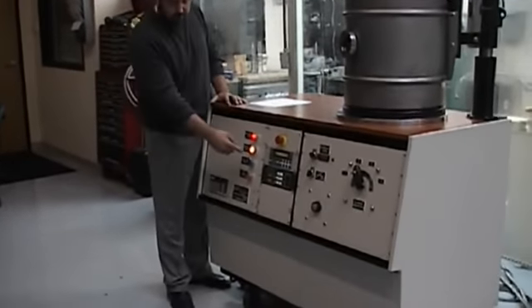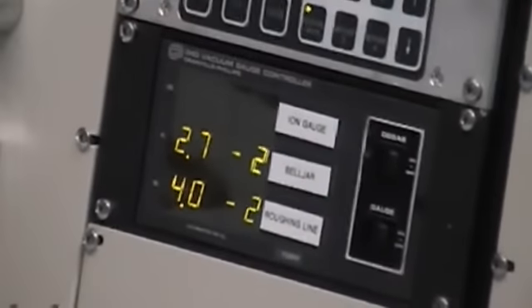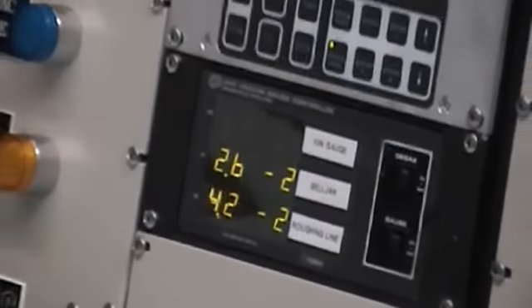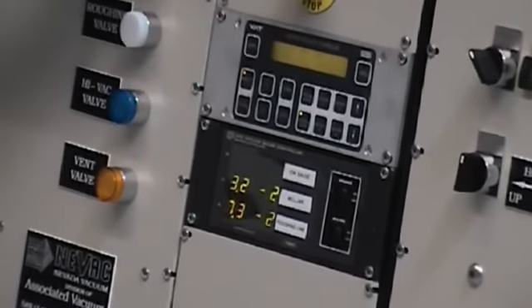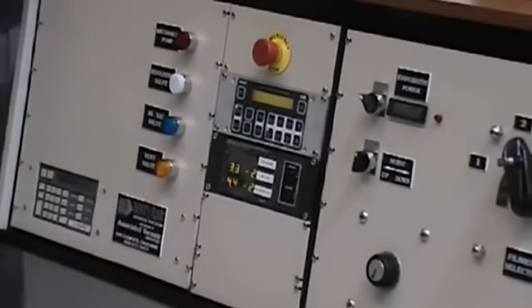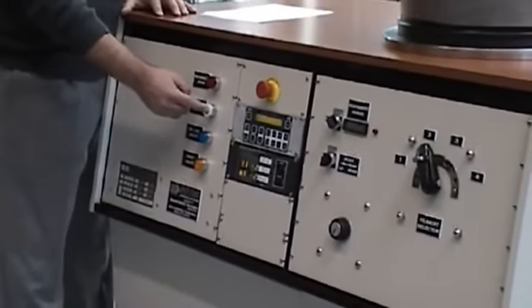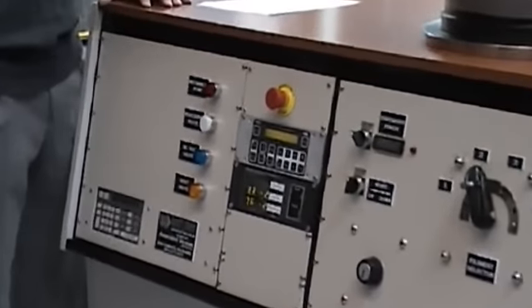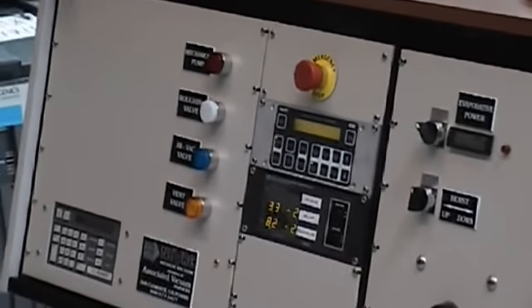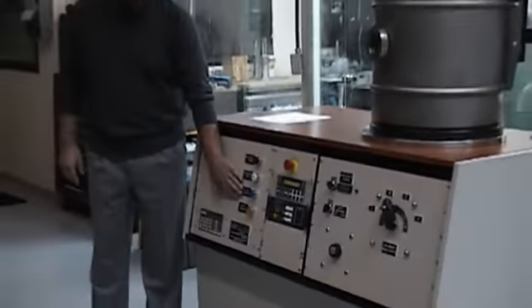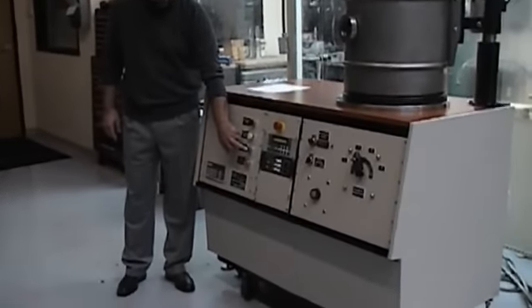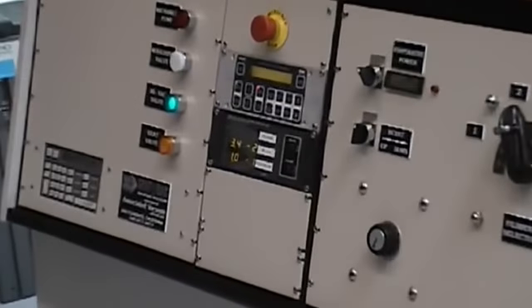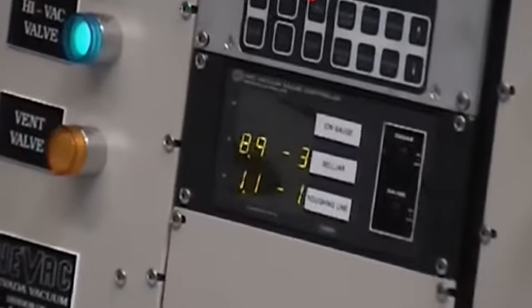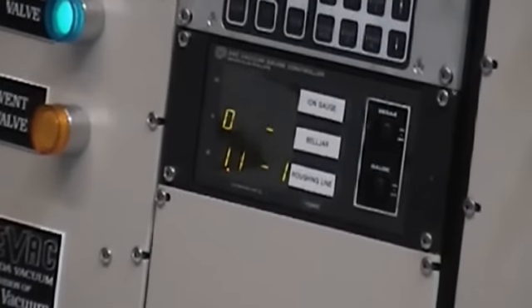Right now we are down to back pressure, 2.7 times 10 minus 2. Again, turn off the roughing valve, turn off the mechanical pump. As you see, the roughing valve is interlocked, it will not operate. Safety feature. Now we run the high vacuum valve, as we did before, and the whole cycle is repeated.